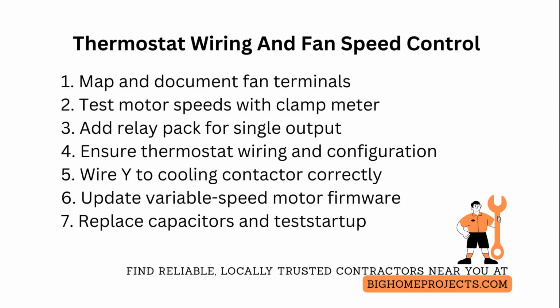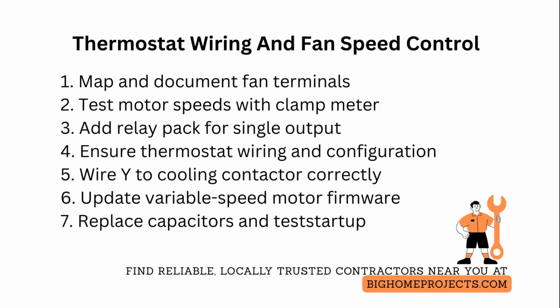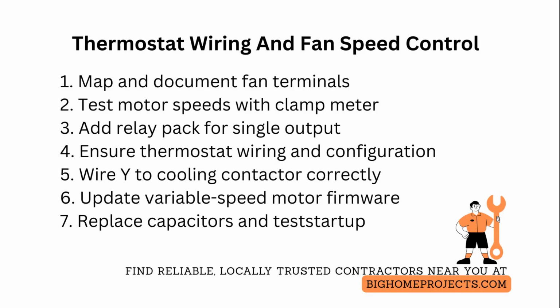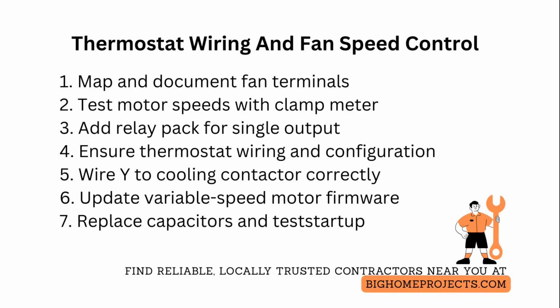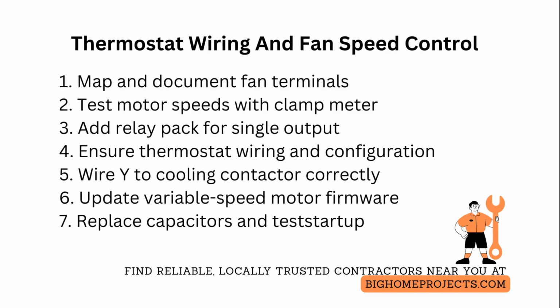Always replace control board capacitors and run a start capacitor test if you see slow spin up on the higher cooling speed, since weak capacitors mimic wiring faults and can damage motors. Finally, after any change, perform a full sequence test: heat call, cool call, fan only, and transition cycles, while logging voltages and currents to a handheld data logger, so you can validate that G and Y calls select the correct terminals and that no unintended overlap or dead zone occurs.